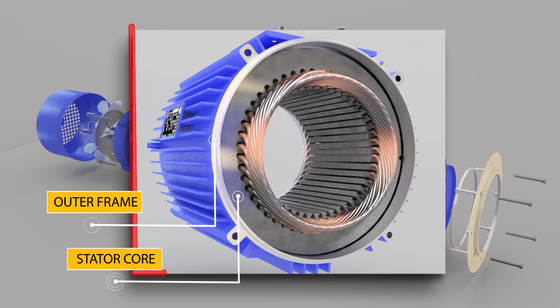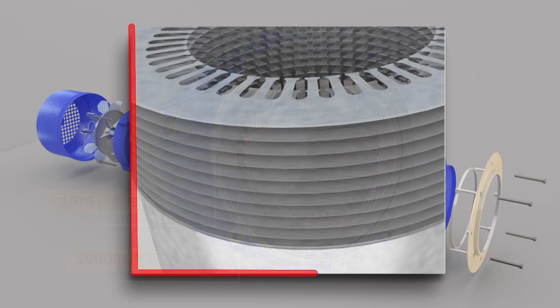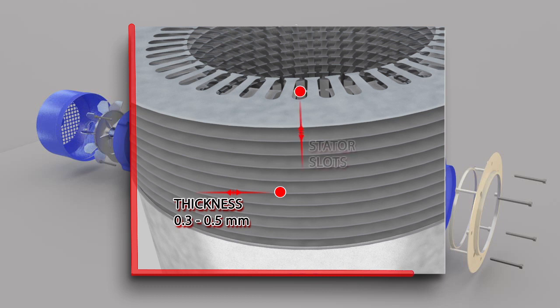The stator core is built of high grade silicon steel stampings laminations. Its main function is to carry the alternating magnetic field which produces hysteresis and eddy current losses. The stampings are fixed to the stator frame. Each stamping is insulated from the other with a thin varnish layer. The thickness of the stamping usually varies from 0.3 to 0.5mm. Slots are punched on the inner side of the stampings.